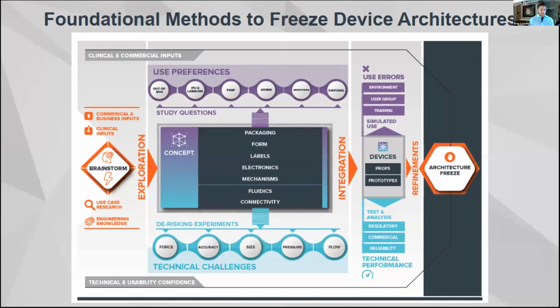So it's a busy canvas, as most device development pathways are quite complex. So I'll try to break this down for you. Where do you start? When there's an existing product, you start from a risk analysis. This allows you to understand where there are maybe shortcomings or maybe even analogous benchmarks in the field that you can test as well. Leveraging human factors analysis and heuristic analyses, existing error reports or complaint data, this can all be leveraged as inputs into your research plan.